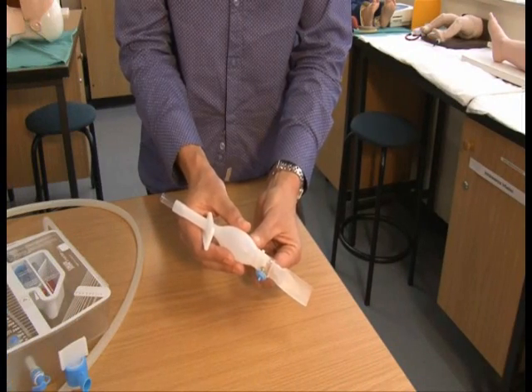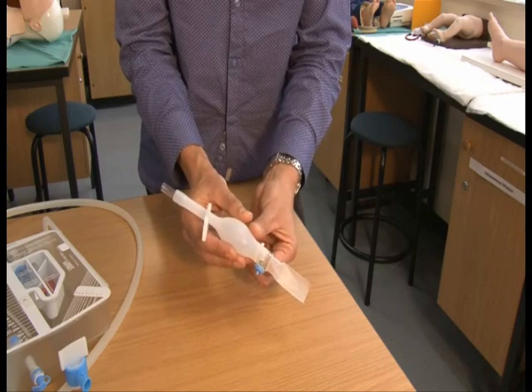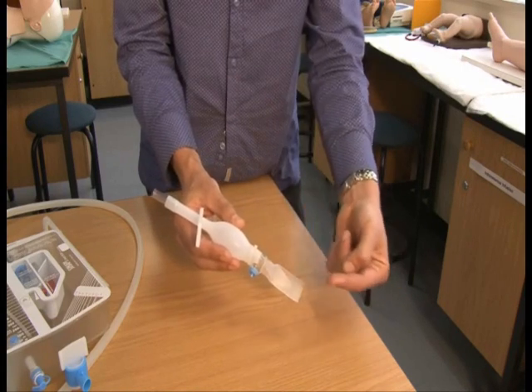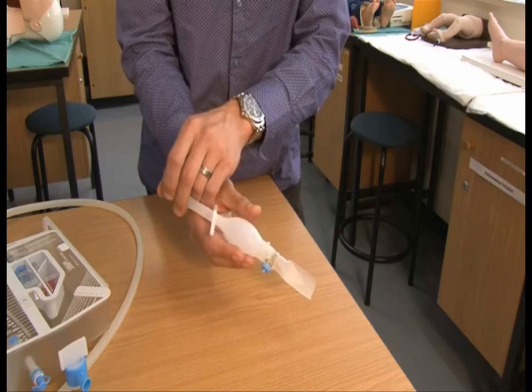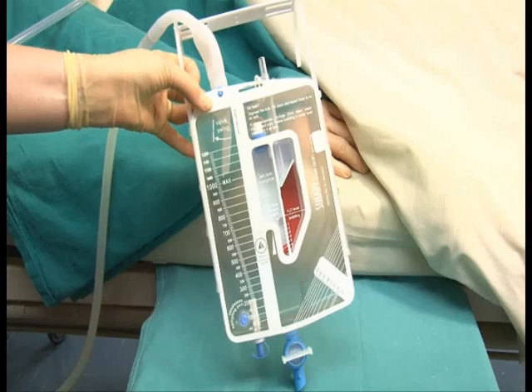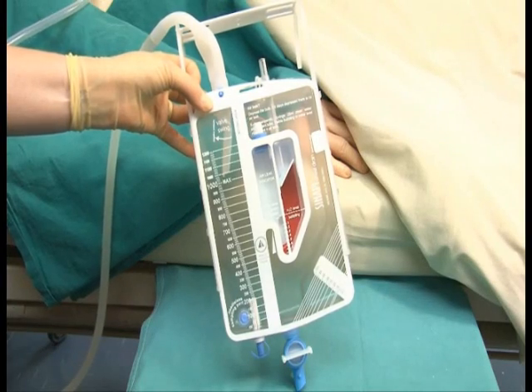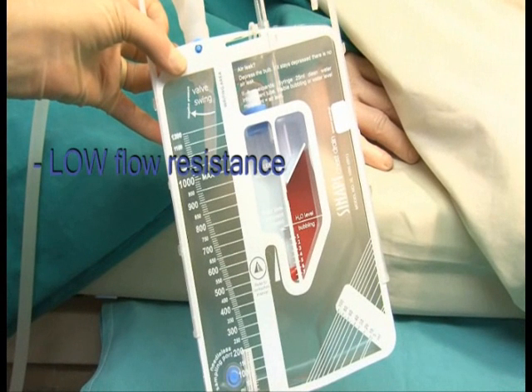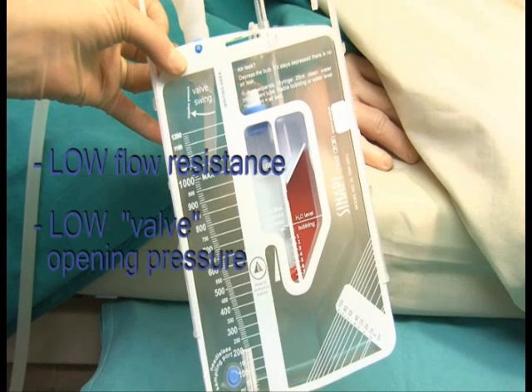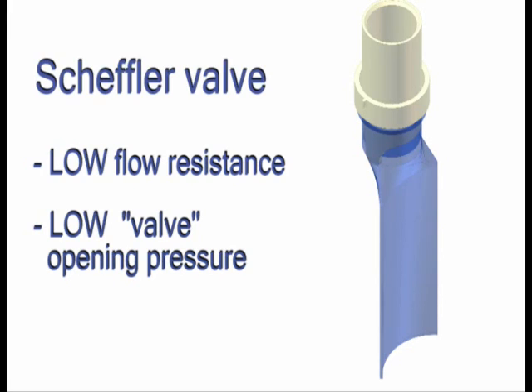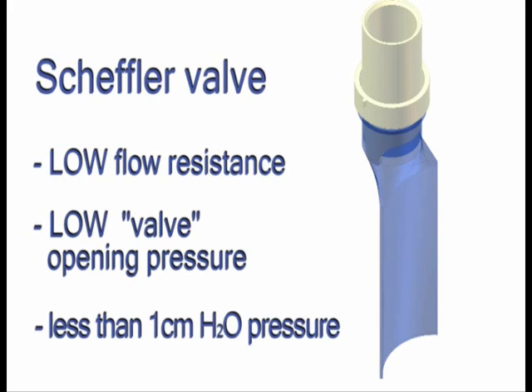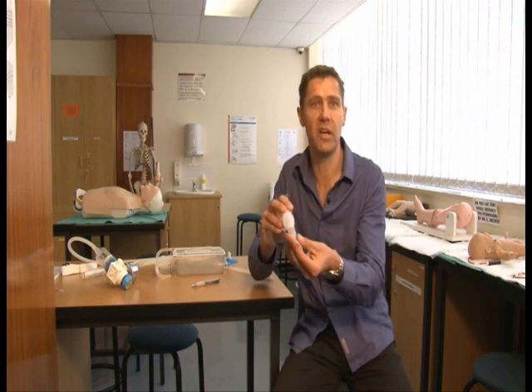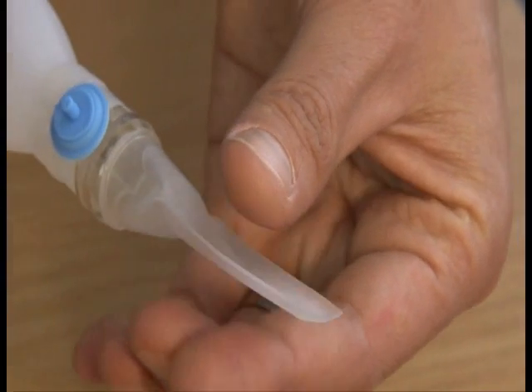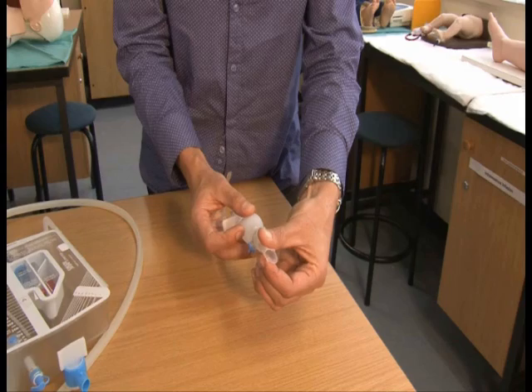The heart of the product is a dry seal one-way valve and low pressure suction bulb combination. The valve ensures no backflow of fluids to the chest and the bulb applies low pressure suction. To effectively drain fluids from the chest, a low flow resistance is required as well as a low valve opening pressure. Our valve is called the Scheffler valve and it has an opening pressure of less than 1 centimeter water pressure. It has a large opening diameter to ensure that solid matter, i.e. blood clots, can drain through it easily.